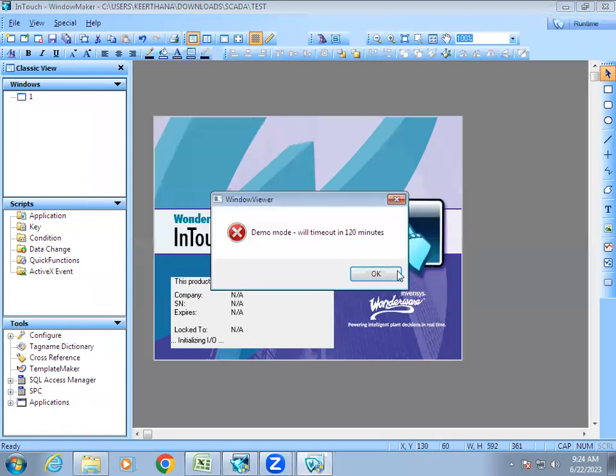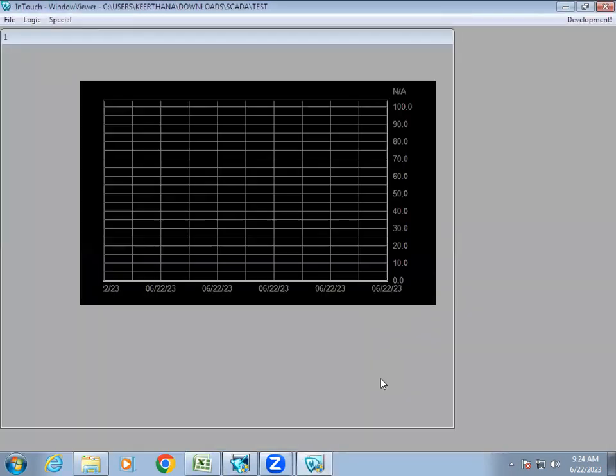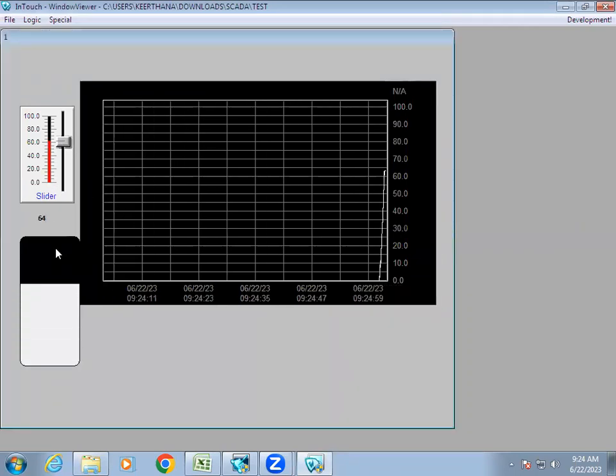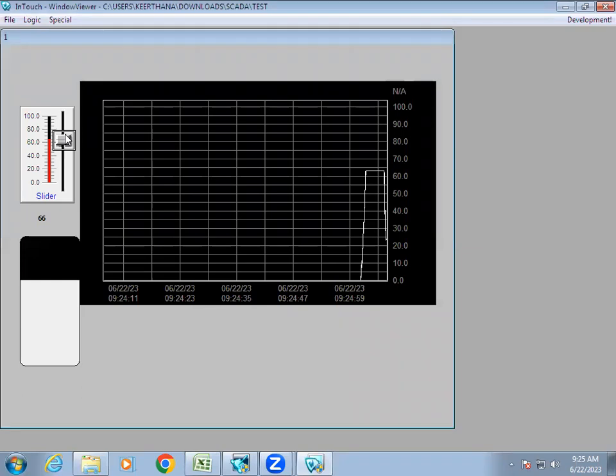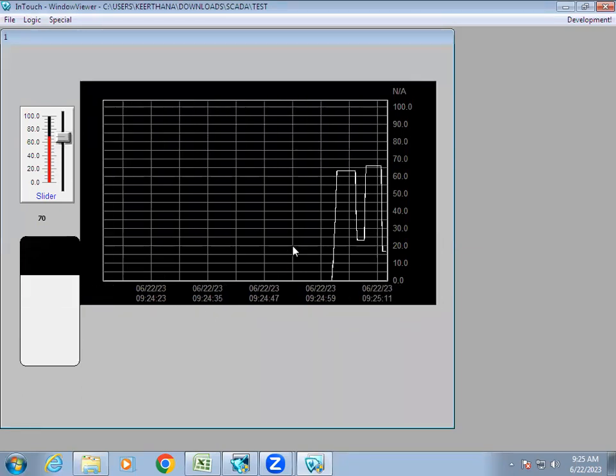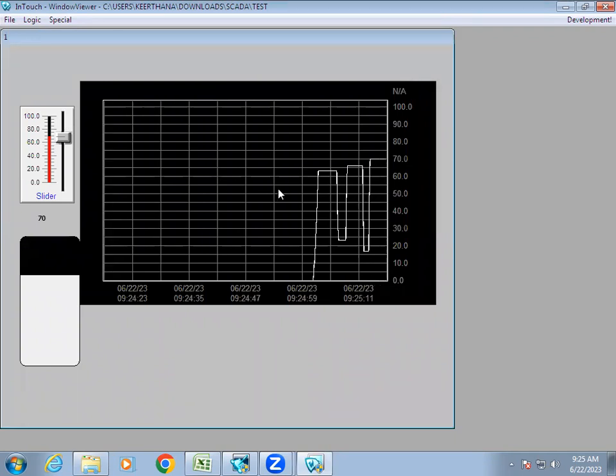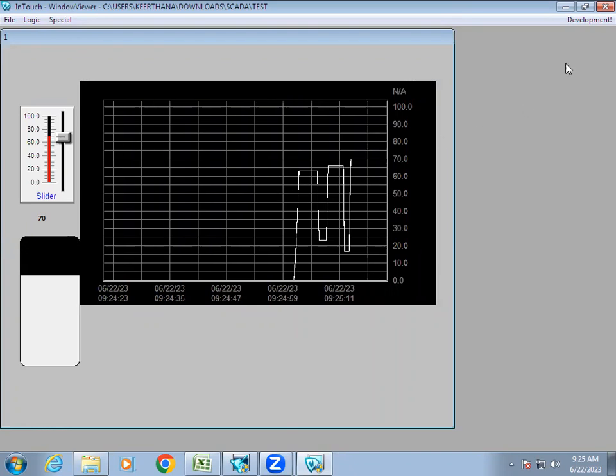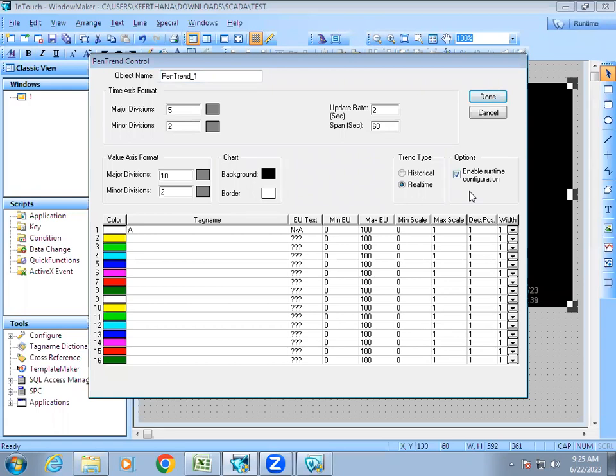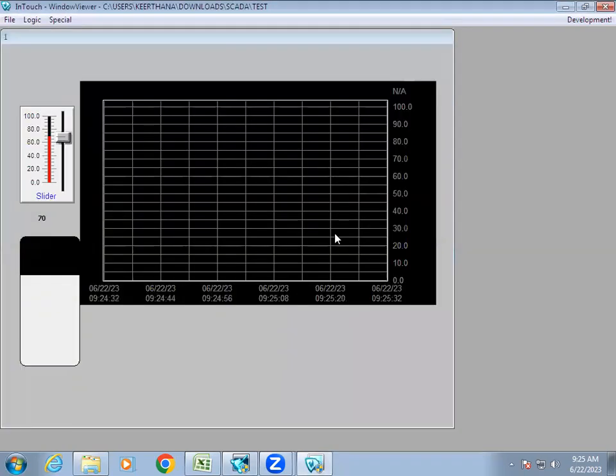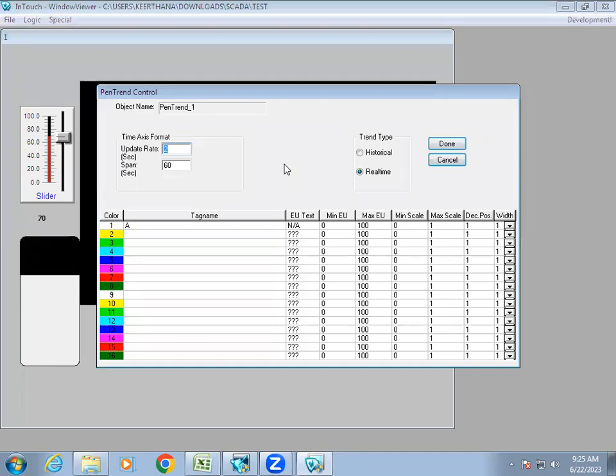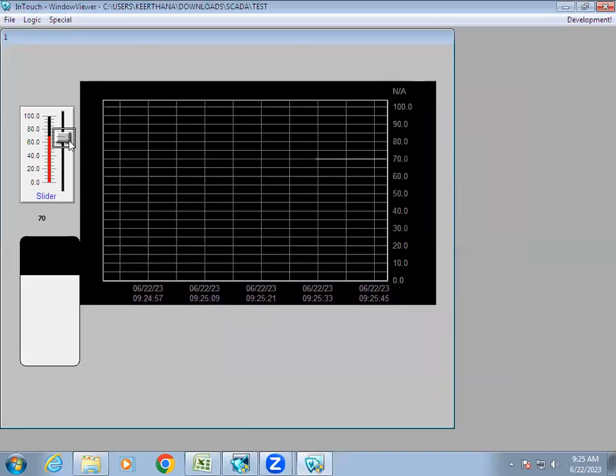Let's go to runtime. When I vary the value you can see it is showing as a graph, but it is taking about two seconds to update the chart — it is not updating quickly. If I want to change the update rate now, it won't allow me because I did not enable runtime configuration. But if you had enabled it, at runtime you can open the chart settings and change the update rate — for example, setting it to zero so changes update immediately.